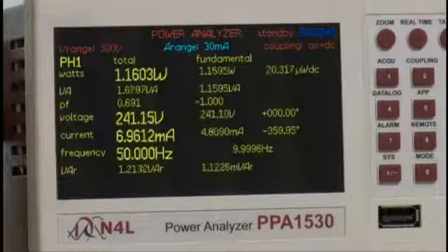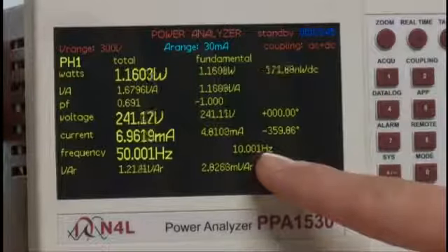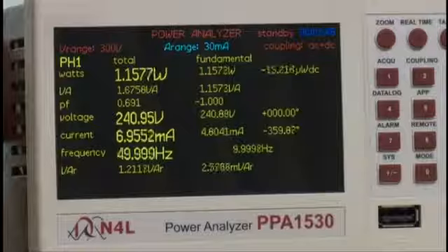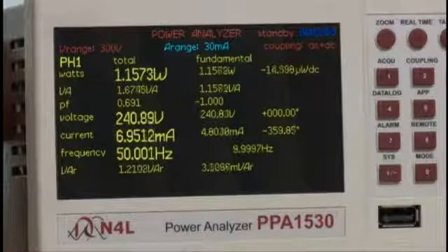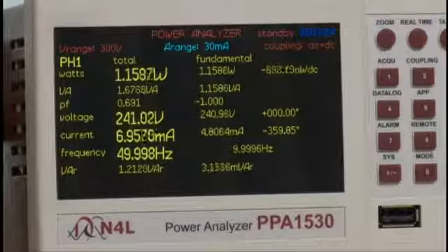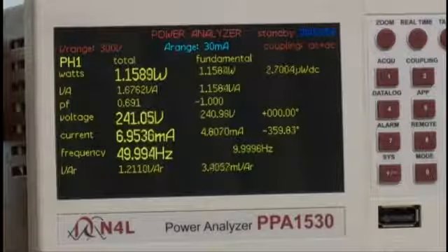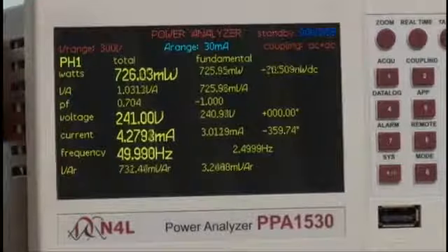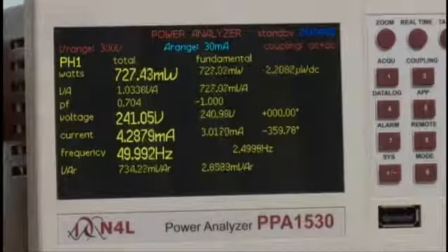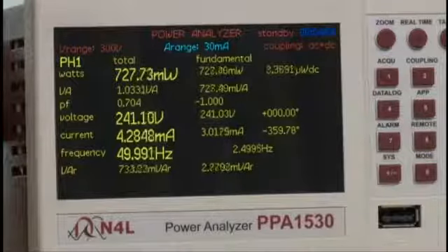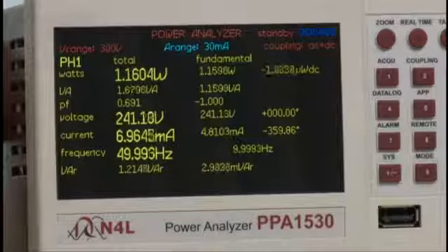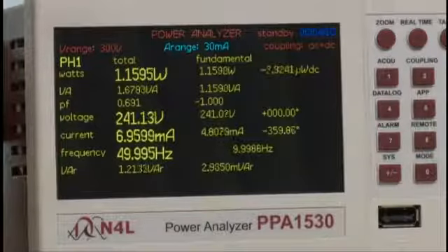At the bottom of the screen, we now see a 10 Hz frequency, which is the period of the pulse frequency, and this period will change depending upon the frequency of the pulse. So if I change the frequency from 1 in 5 of the 50 Hz cycle to 1 in 20, it can be seen that the measured pulse frequency changes from a 10 Hz period to a 2.5 Hz period.